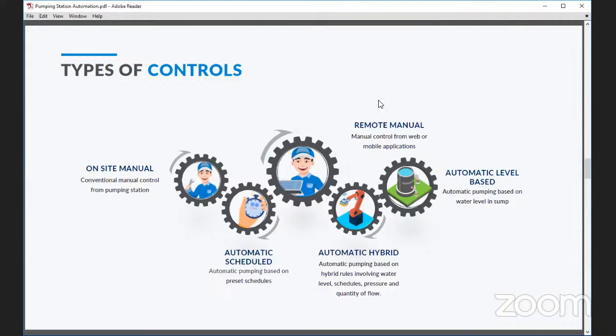So this is the most advanced kind of control that's called automatic hybrid. All these events, anything done from the remote on-site manual person, from the remote server manually, or from the remote server automatically, or in a hybrid way, all of this is logged into the IoT gateway, and the IoT gateway keeps reporting all this to the server. So end of the day, we have a complete activity list that happened in the pumping station that we have access to see - what went wrong, why the pumping was stopped, why the pump had failed, and all that. So this is the advantage of this kind of pumping system.